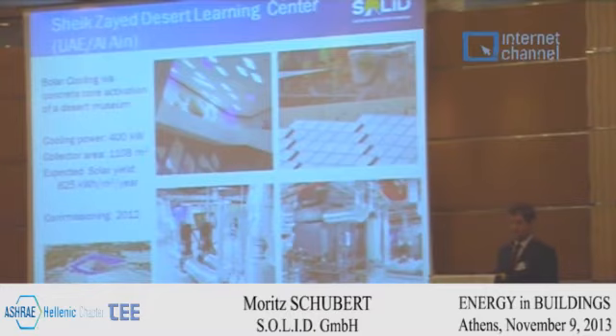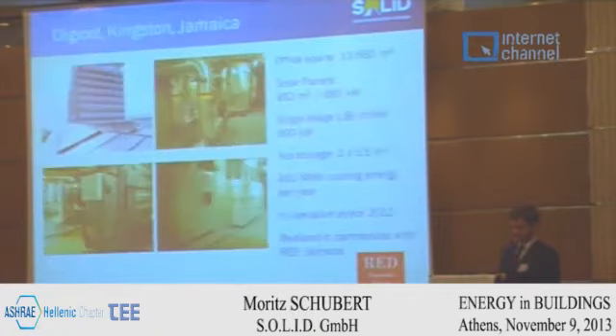The driving temperatures needed for solar cooling machines are not as high as if we feed into a ventilation system. The cooling power is 400 kilowatt from the absorption chiller machine. Obviously, it's not enough to cover the whole building, but this core activation can substantially contribute to it.